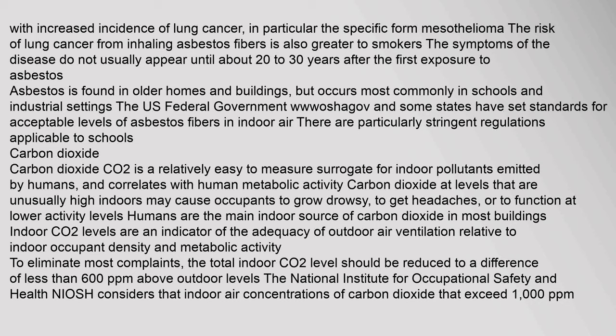Carbon dioxide (CO₂) is a relatively easy-to-measure surrogate for indoor pollutants emitted by humans, and correlates with human metabolic activity. Carbon dioxide at levels that are unusually high indoors may cause occupants to grow drowsy, get headaches, or function at lower activity levels. Humans are the main indoor source of carbon dioxide in most buildings. Indoor CO₂ levels are an indicator of the adequacy of outdoor air ventilation relative to indoor occupant density and metabolic activity.